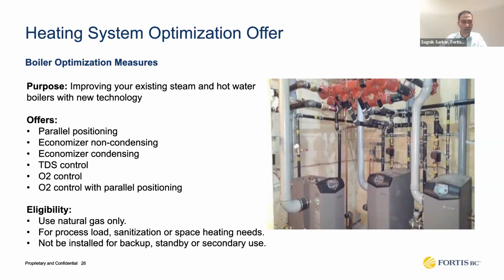So the offers we have are parallel positioning. Parallel positioning is something like cooking on a gas stove where you're adjusting the flame. In parallel positioning, you're adjusting the air as well. By air, I mean oxygen. So whenever you're increasing or decreasing the boiler burning rate, the air is getting adjusted as well, improving the efficiency.